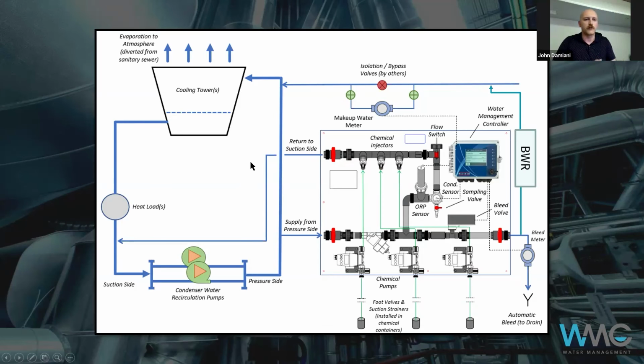So on the closed loop side, you definitely need filtration, just like any closed loop, whether it's heating, cooling, chilled water, glycol, anything needs filtration, because there are corrosion byproducts that will always come out and will foul the system if you don't filter them out. And then you need some sort of treatment. You usually have either a manual pot feeder, or if it's a large system, you could meter and pump chemical into it. So you'll have some sort of inhibition in there if it's not direct use water.